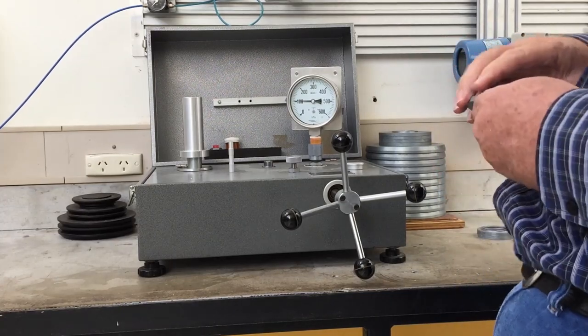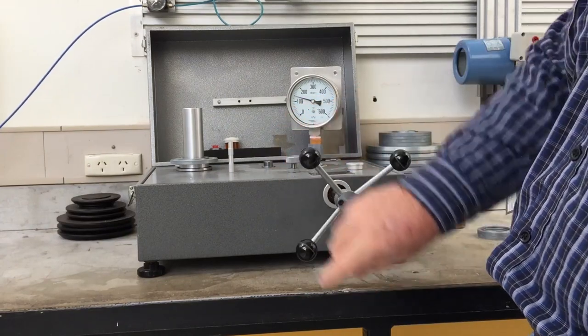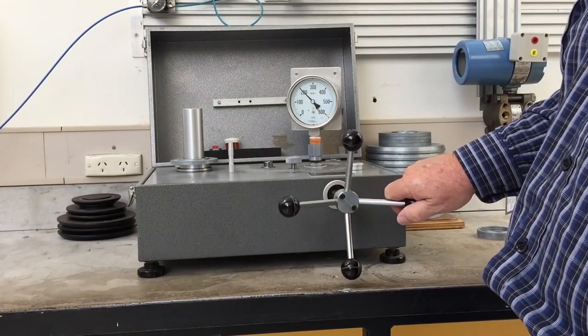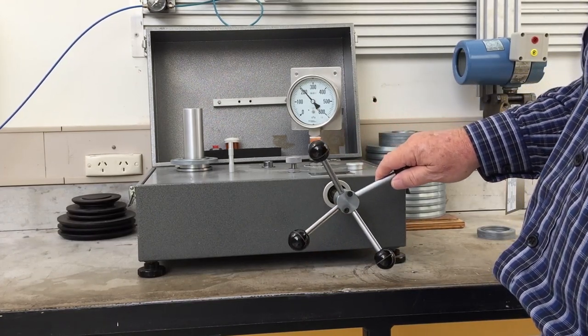Add the next weight to take the next reading. In this case, 100 kPa is added to make a total of 200 kPa. Increase the pressure by turning the handle and record the pressure on the gauge when the piston pops up.